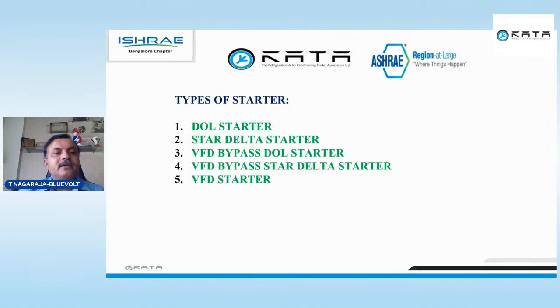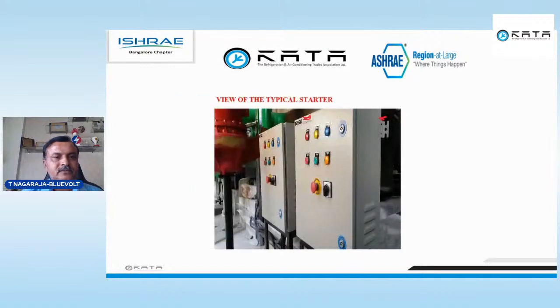DOL starter now means everything we can hook to the BMS also: auto manual status, run status, trip status, in command, whatever is there. Further, there are some smart device starters that can even be integrated. All the parameters it is showing, even voltage, current, and the percentage it is running, can be integrated directly without using any controllers. Some manufacturers make these. I think these typical starters you can generally see.